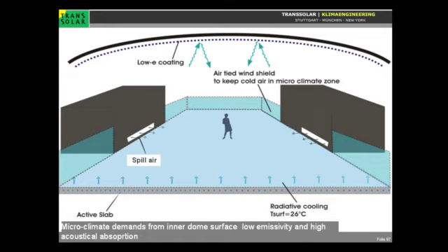This also requires the inside of the dome to have a low-E coating, because up there we easily reach 50 degrees Celsius, and we don't want to stand below a radiator burning us with that heat. The low-E coating means it doesn't emit heat and instead works like a reflector—our Bangkok airport approach, which hopefully isn't flooded these days. The cold floor, rather than the hot ceiling, gets reflected. Visually, if the ceiling were a mirror, looking up you'd see the floor. The same works with thermal radiation: you don't see it, but your body senses the long-wave radiation from the floor reflected in the ceiling instead of the ceiling's high temperature.